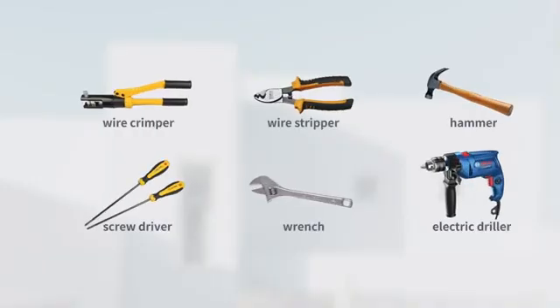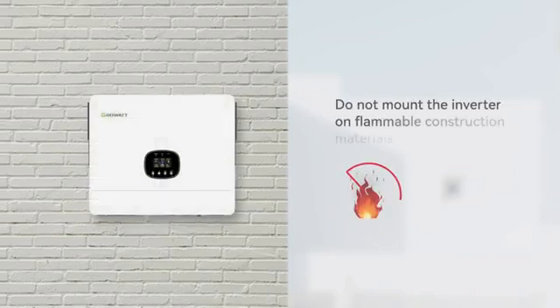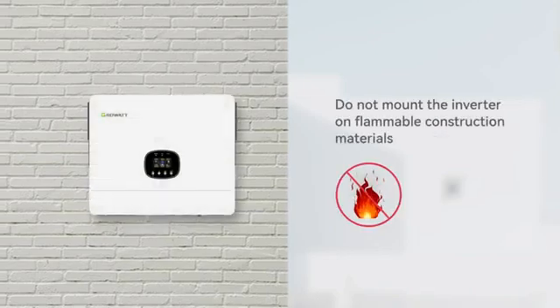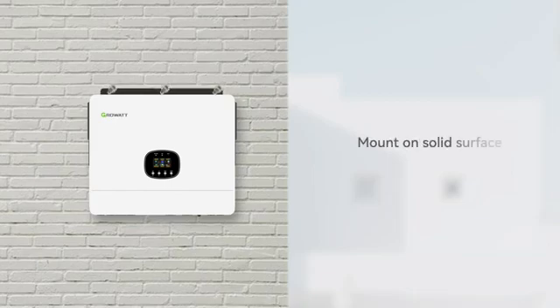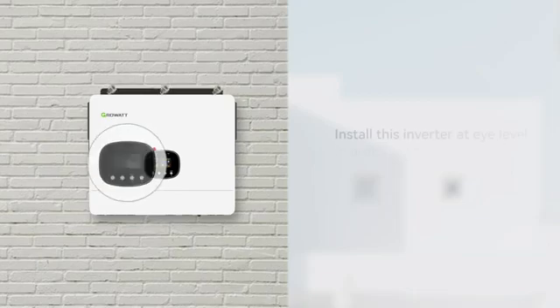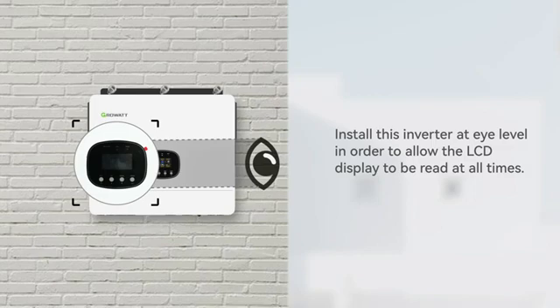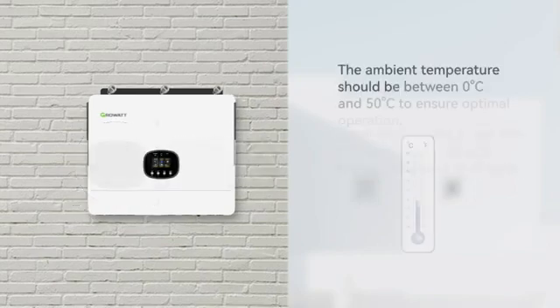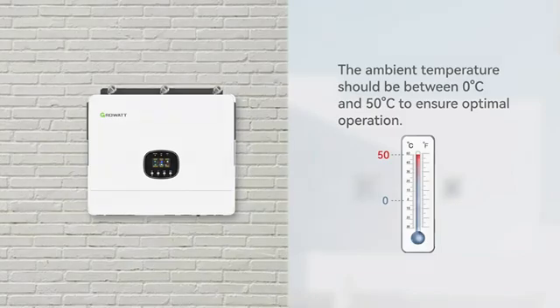Before installation, prepare the necessary tools. Do not mount the inverter on flammable construction materials; mount on a solid surface. Install the inverter at eye level to allow the LCD display to be read at all times. The ambient temperature should be between 0 and 50 degrees Celsius to ensure optimal operation.